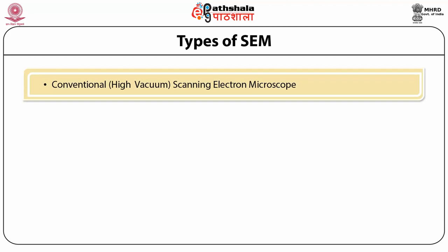The first type is the conventional scanning electron microscope with high vacuum, which is the most common type. It requires a dry, conductive sample, which can be achieved by applying a thin layer of metal to the surface using a technique called sputtering. The sample must be able to withstand high vacuum. This type of machine is used for routine imaging using either secondary electrons or backscattered electrons, with both secondary electron and backscattered electron detectors fitted to display images on a computer.